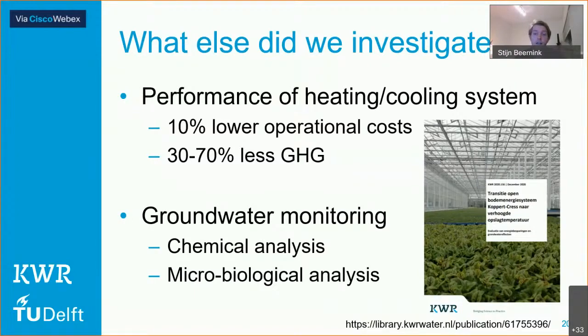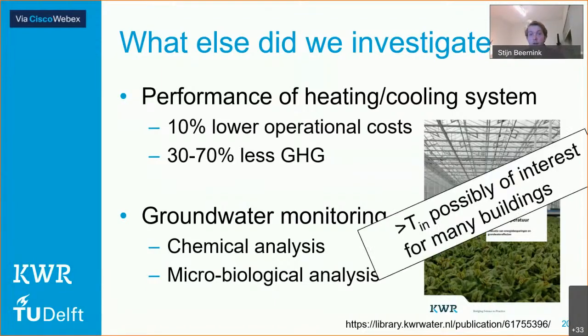And we also did, as I told you, groundwater monitoring, and we did chemical and microbiological analysis of these samples. And we found that most effects that we found were due to the mixing of those two aquifers. So that is also something you have to think about. So overall, I think a take-home message would be that higher storage temperatures for your warm wells is a really nice possibility for many buildings that now have only a lower temperature warm well.